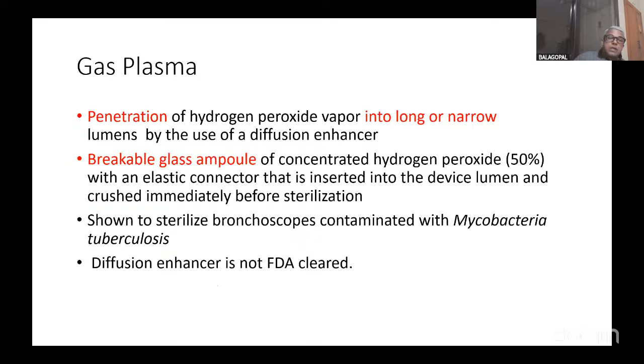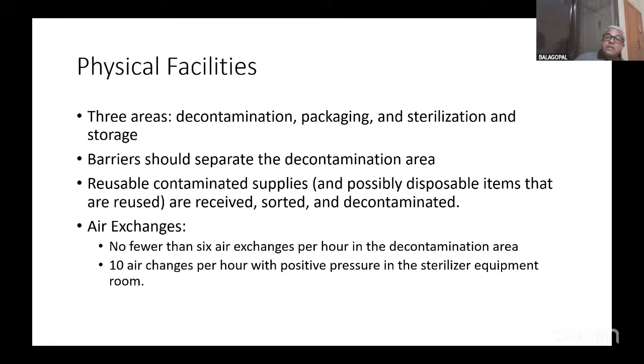I've been interested in storage and packaging also, as a topic. It involves decontamination, packaging, sterilization, and storage. The storage area should have barriers and should be separated from the decontamination area. Reusable contaminated supplies are received, sorted, and decontaminated in these areas. There are specific criteria about the air exchanges required: 6 air exchanges per hour in the decontamination area, and in the sterilizer area around 10 air exchanges. This is how it should be arranged.